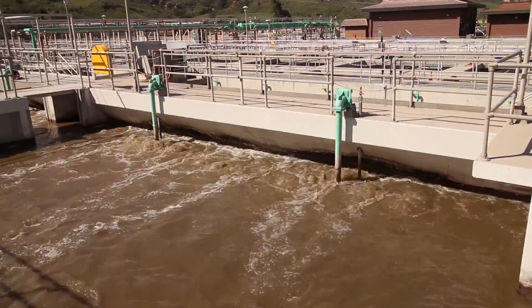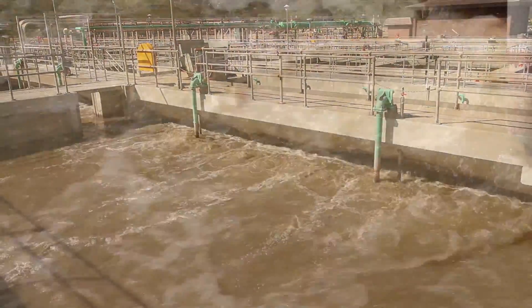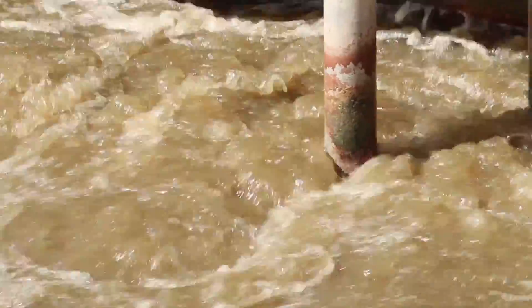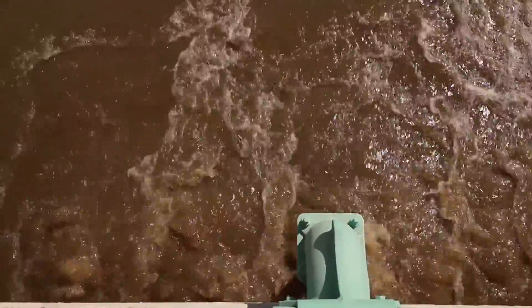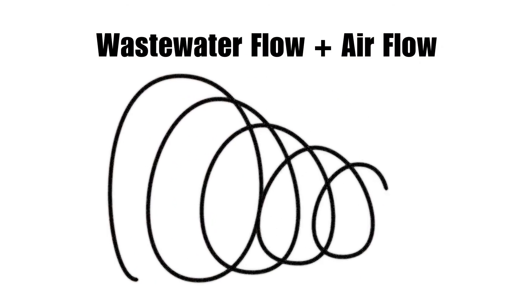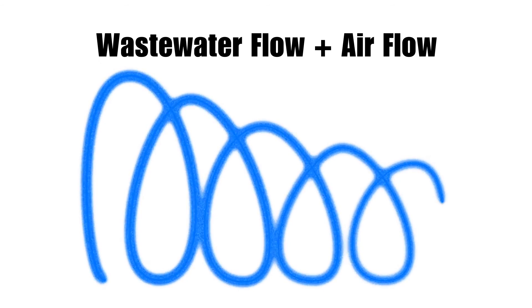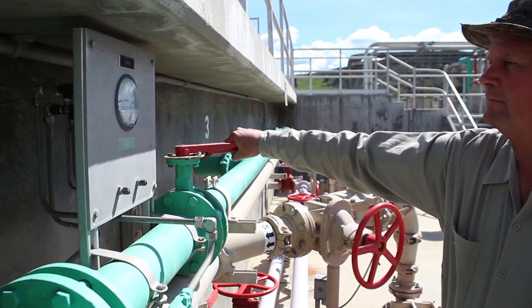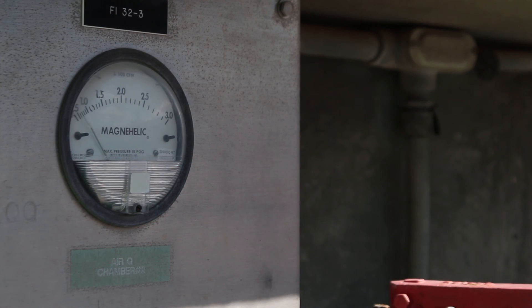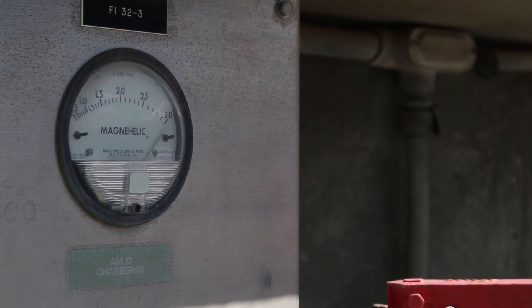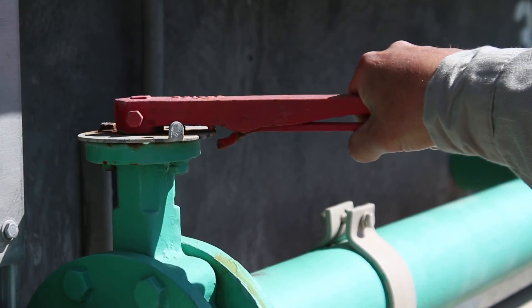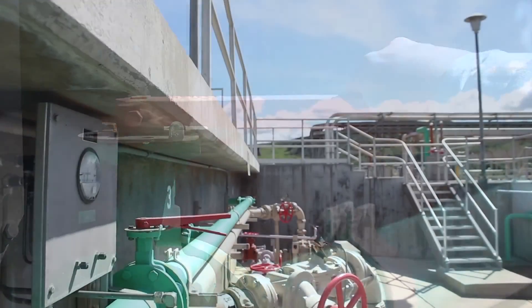These aerated grit chambers are divided into two segments. Each segment is equipped with a diffuser for injecting air and a hopper for collecting the grit. As the wastewater flows longitudinally through the grit chamber, air is injected so that it produces a rolling action across the width of the chamber. The combined effect of the wastewater flow and the airflow creates a spiral flow pattern, causing the grit to settle out and accumulate in the hoppers. The amount of air sent to the grit chambers is critical — not enough air will allow organic material to settle out and too much air will keep the grit in suspension. A butterfly valve is used to throttle airflow to obtain the optimum airflow.